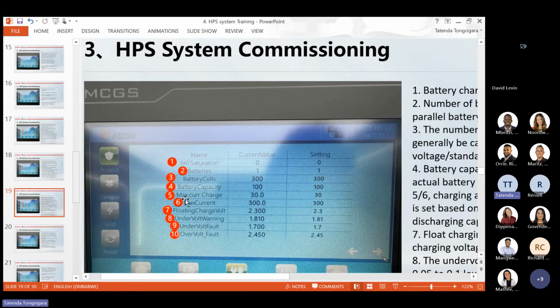And then the only difference is on max current charge and max current discharge. If you have 5 batteries charging at 100 amps each, you just write 500 if the discharge is also 500, or say half of the total charge current of the batteries. So 5 times 100 is 500, divided by 2, you can write 250, 250, or if it's 1C, you write 500, 500. But these values should not exceed the charge current displayed on the HPS nameplate. So you just verify with the nameplate, on the door or on the left side, what your max charge current is.